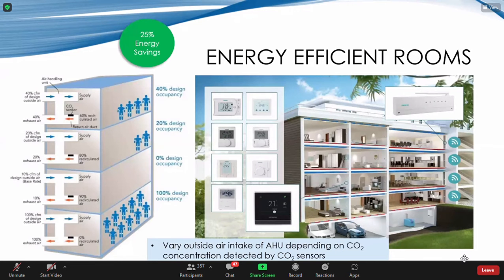Moving on, that's just a sample of how you can do total room automation. Basically it's a very simple concept: make everything variable depending on demand. So it's a demand control, demand-supply approach. If there are few people, you adjust the air intake, you adjust the lighting when there's no one around. That's why automatic lighting in CRs and toilets needs sensors installed.